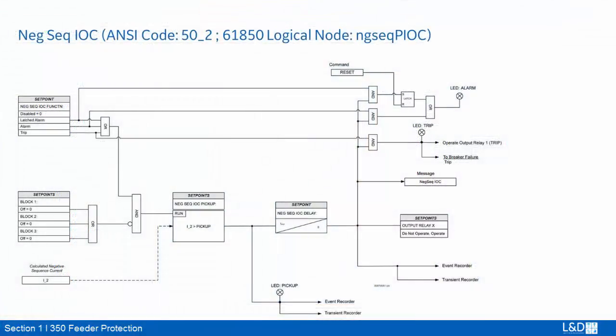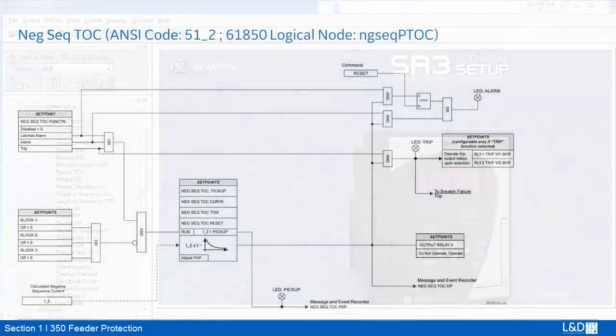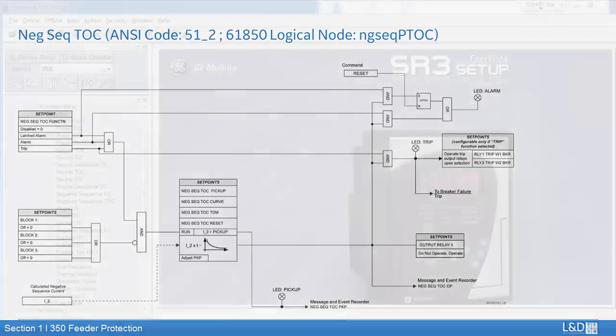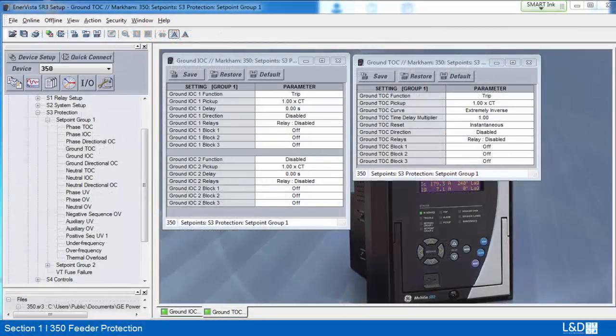From the logic diagram of negative sequence IOC and TOC, we can see the input current I2 is the calculated negative sequence current. For the calculation of the inverse curve, the multiple should be negative sequence current over the CT rating. Ground IOC and TOC use the ground input D6/E6 measured current as the operating current.